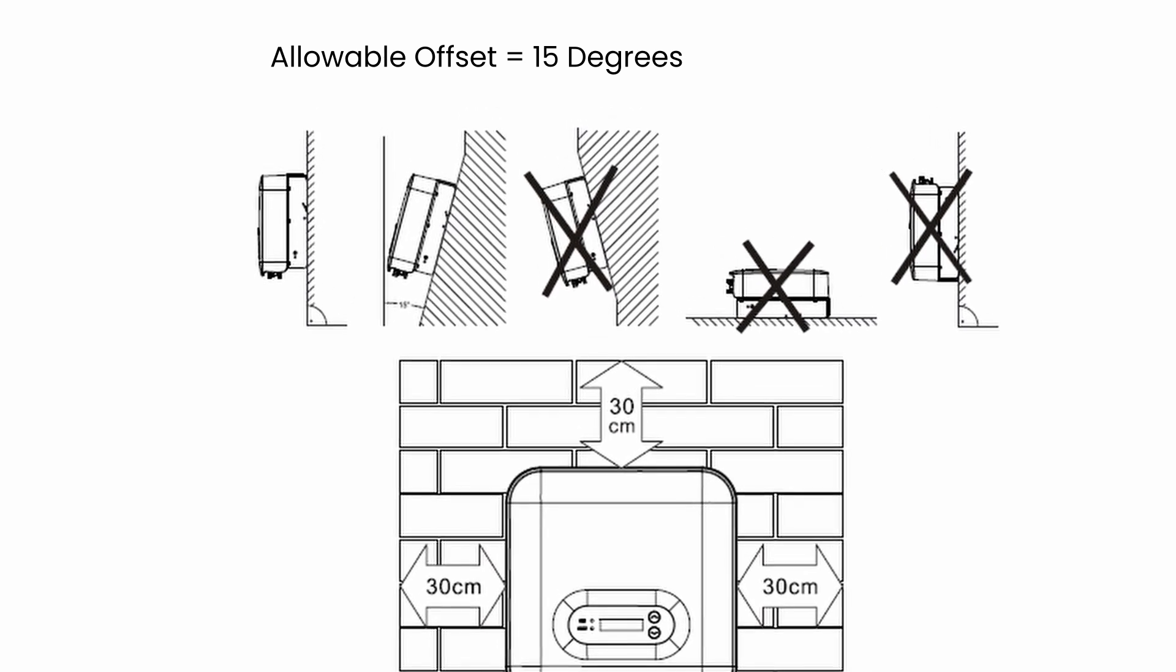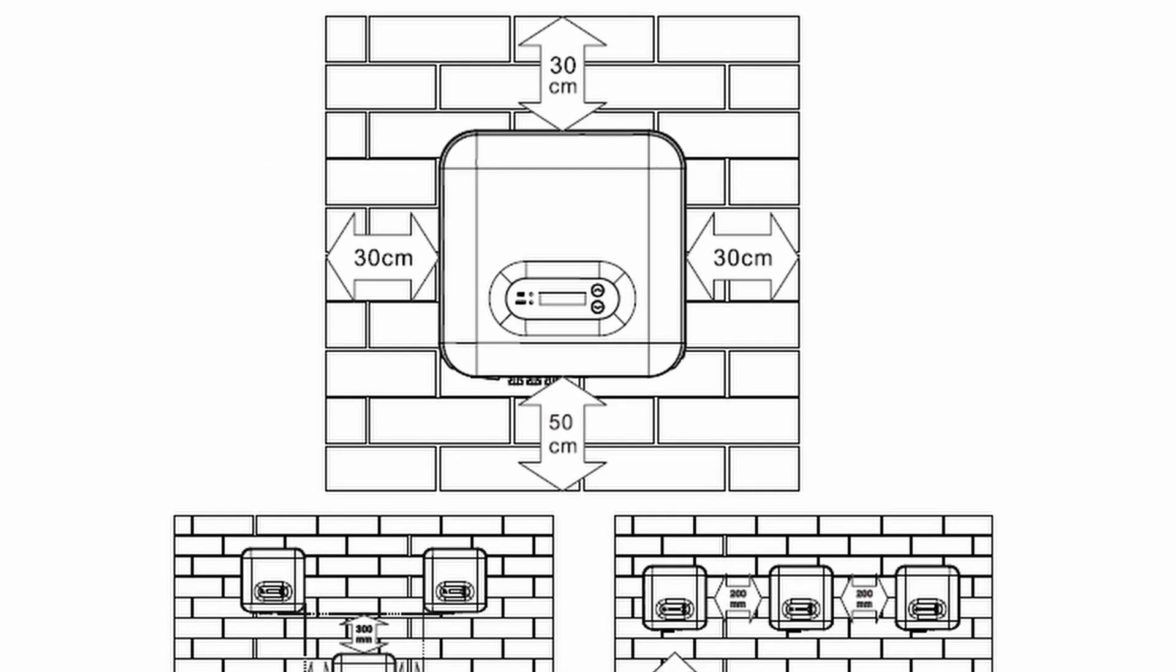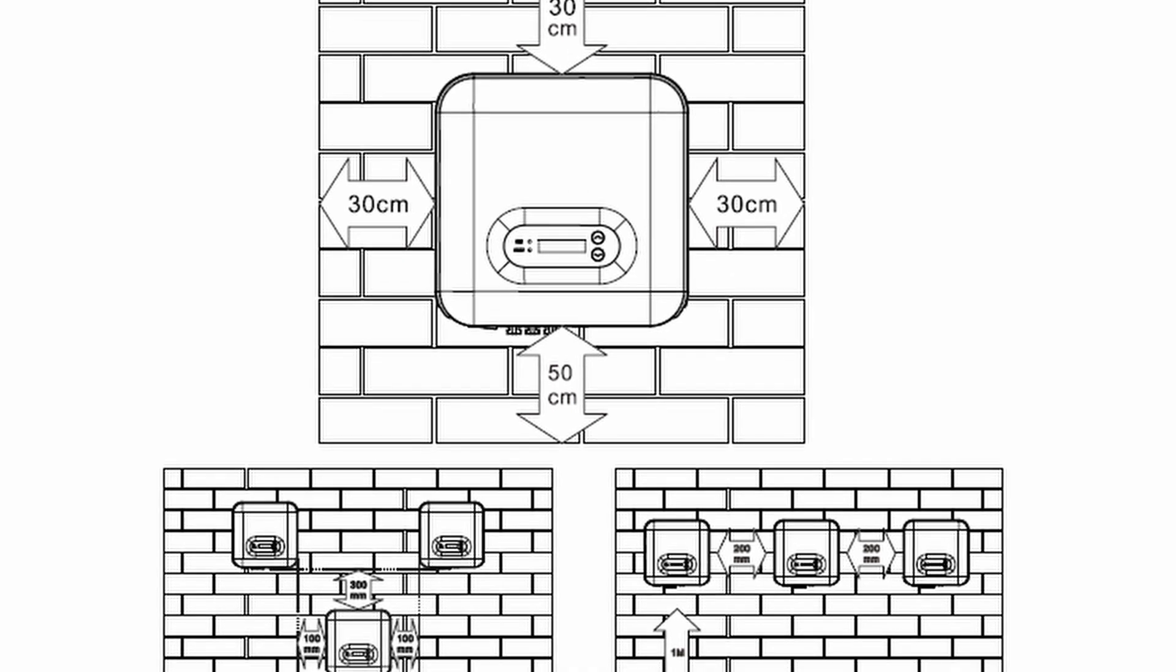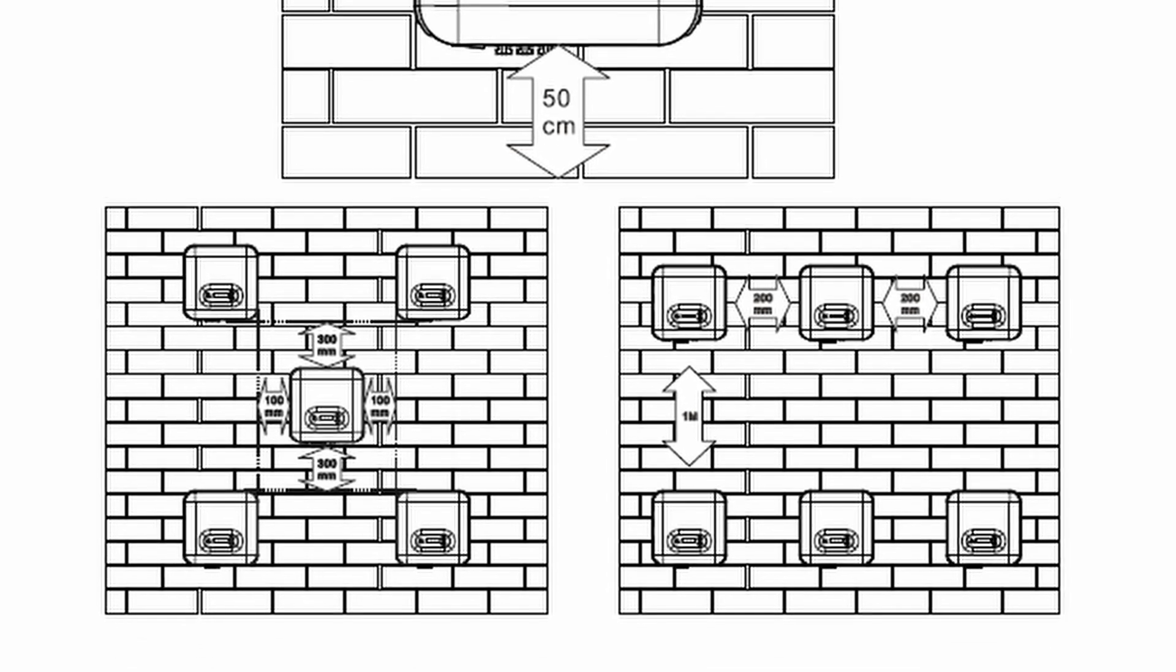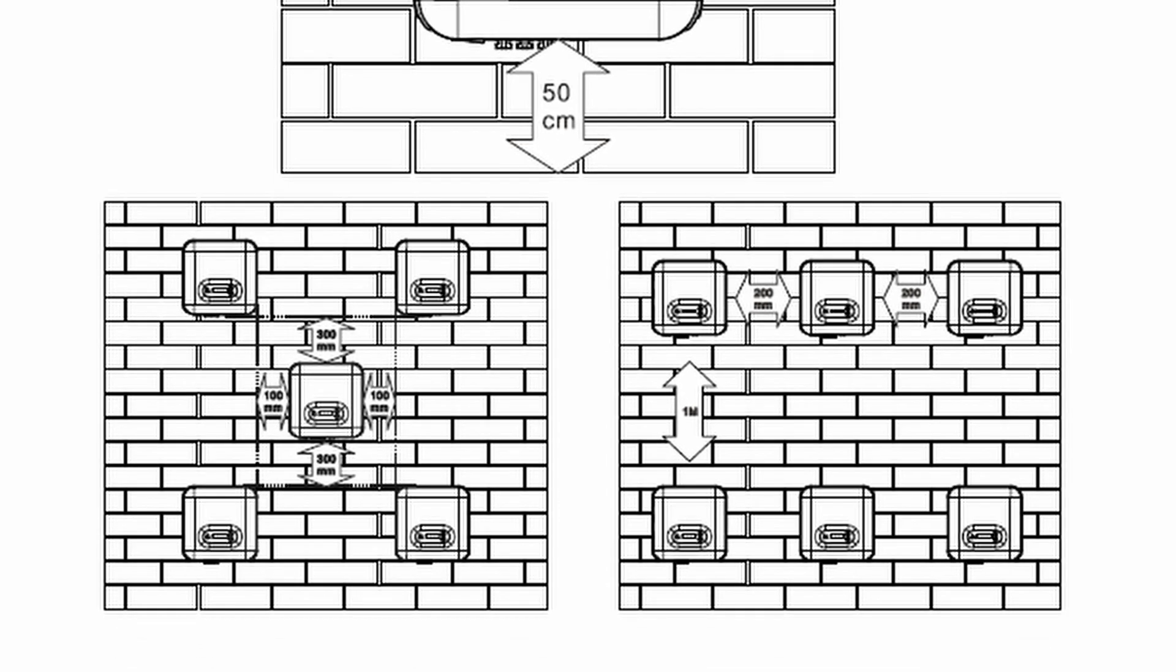Keep minimum distances of 30 centimeters from the sides and top of the inverter from any obstacles, and 50 centimeters from the bottom. This is for proper ventilation. If you need to fit more inverters, you need to keep those distances between them as well.